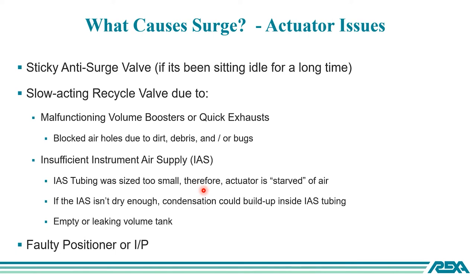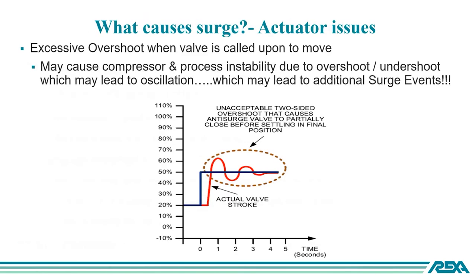And last but not least, also a faulty positioner or an I/P that could not be operable, and thus create some fault conditions with the anti-surge valve as well, right? If the quick exhausts or the volume boosters are not tuned correctly with the compressor control, that could lead to excessive overshoot. And that is something that happens a lot, especially when you start adding a lot of volume boosters and quick exhaust.